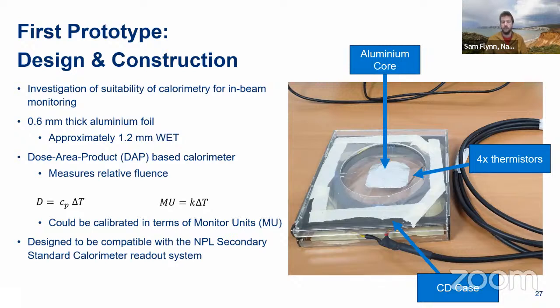This is technically a dose area product calorimeter because it is larger than the beam that it is measuring. We envision that if you were to ever use this, not that I would recommend using this particular device, you'd calibrate it in terms of temperature change, which would be done against a device at reference conditions, similar to how you would with a monitor chamber, in terms of monitor units or something. The readout for this device was designed to be compatible with the secondary standard calorimeter that I showed earlier, using the same circuits.